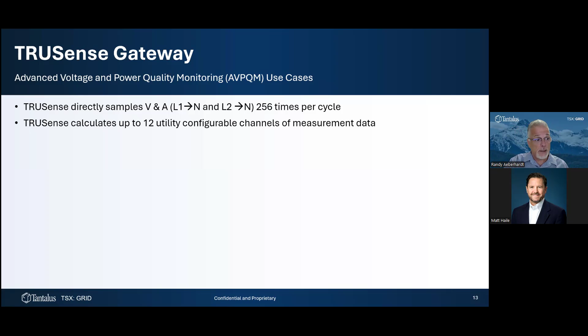With this kind of information, you can set up alarms within the device to detect true loose neutrals—if the voltage between line one and line two differs by more than a configurable amount, you get an alarm and a waveform capture, so you now know you've got a true loose neutral. We can also get waveform captures with your blinks, and we can count a blink down to a single cycle.